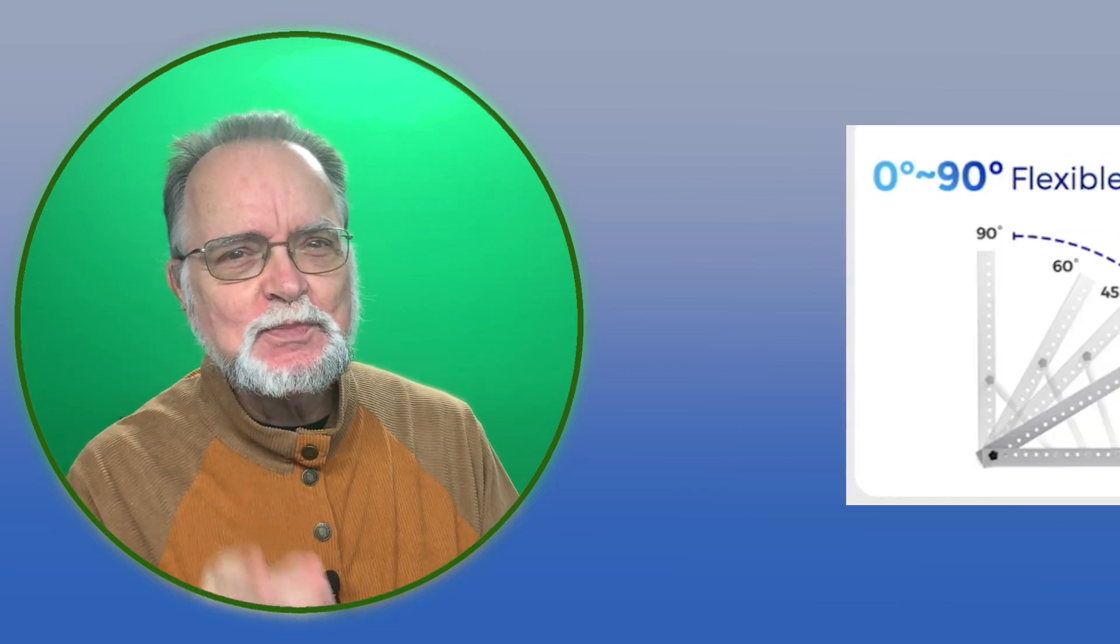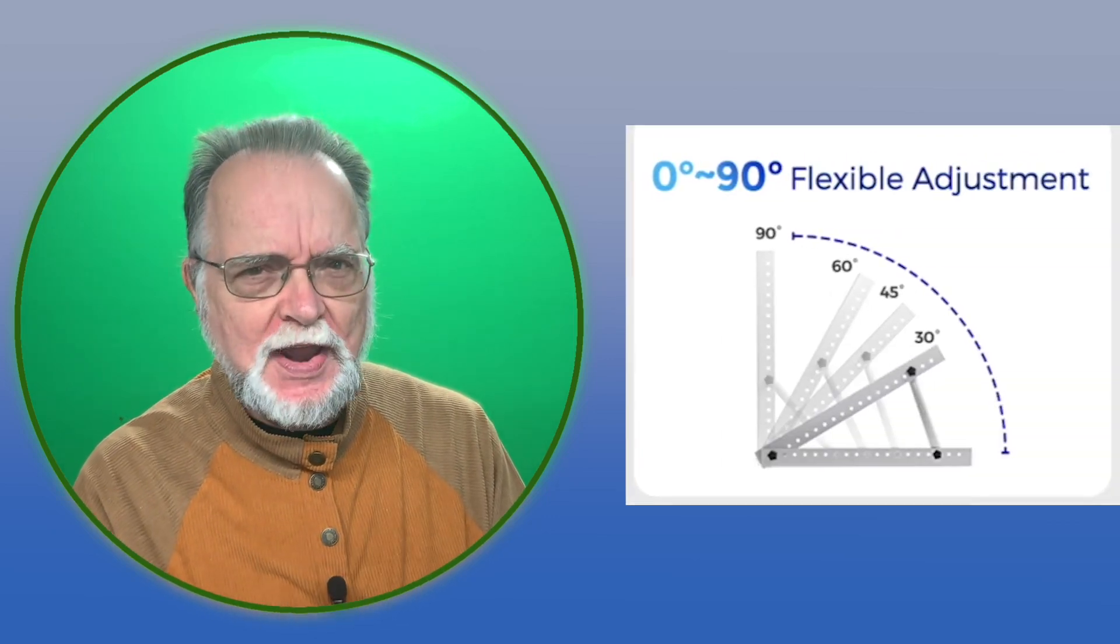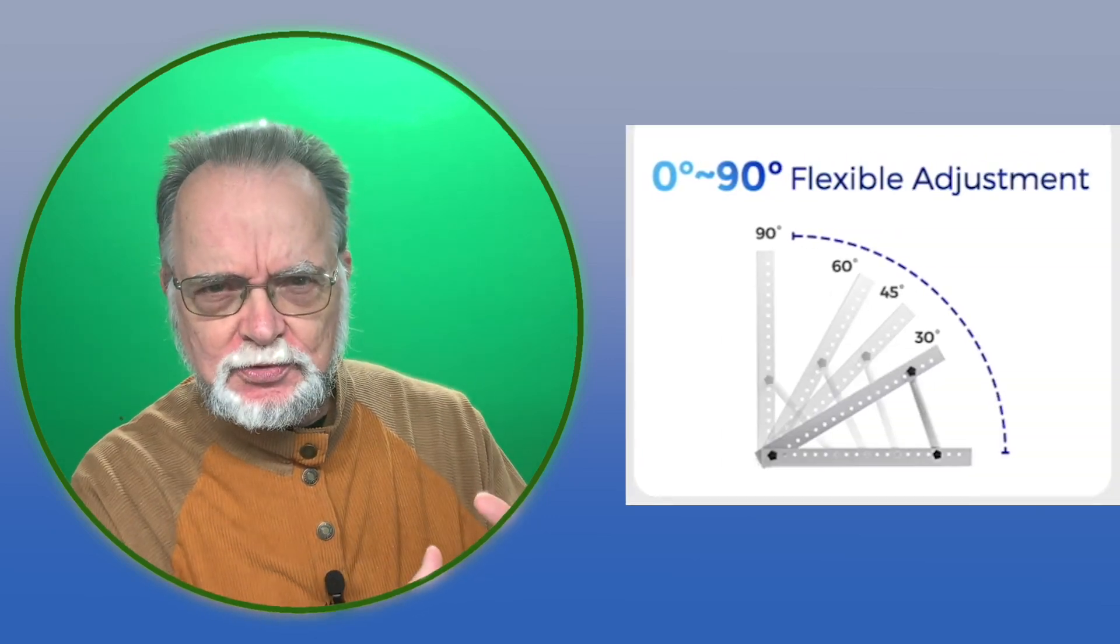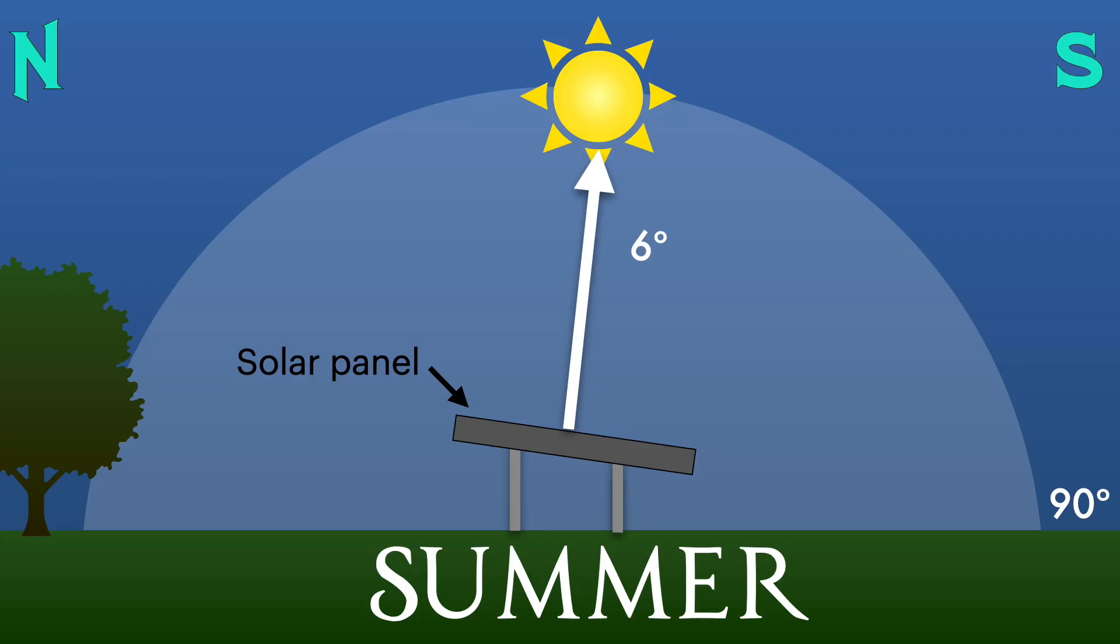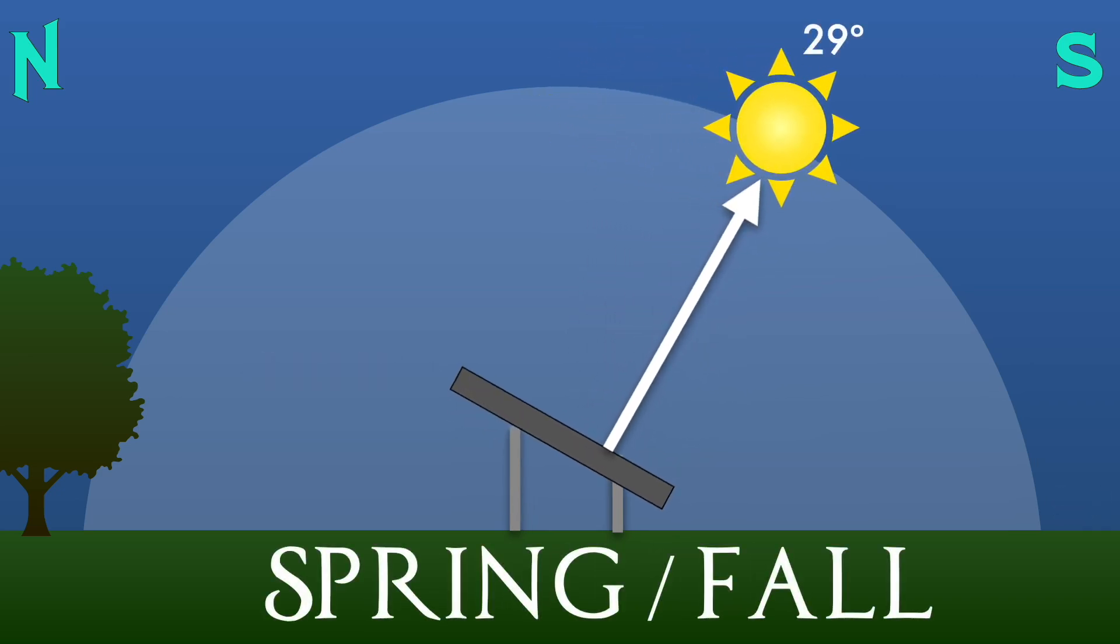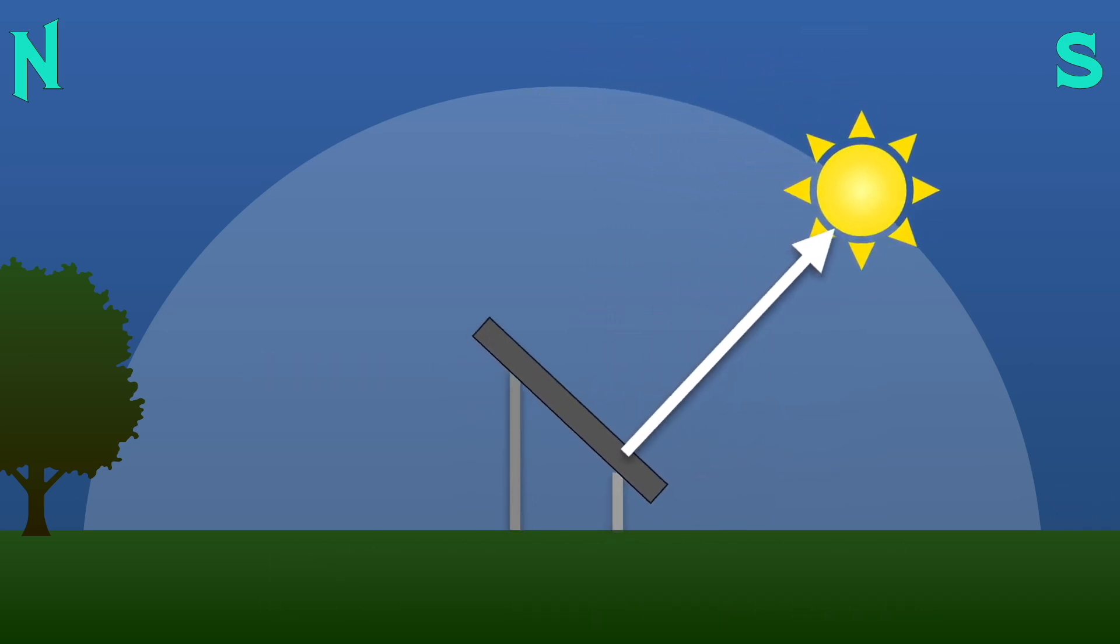You can get even more gains by using a variable tilt rack mount and changing the tilt of the panels for each season. So in the summer my panels would be aimed at 6 degrees, in the spring and the fall at 29 and in the winter way down at 52.